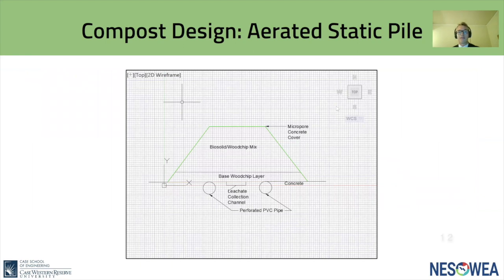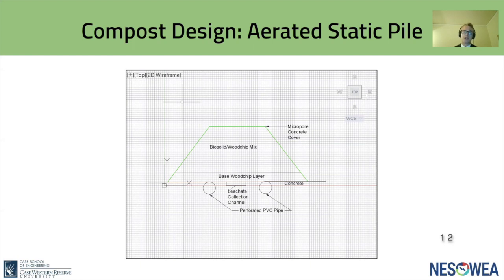We have chosen the aerated static pile composting method. This method involves the placement of a mixture of organic matter and bulking agent onto a system of perforated pipes which forcefully aerates the concoction. Aeration is key, as the process relies on micro-organisms breaking down the organic matter while consuming BOD. We also considered the windrow method, which similarly requires compost placed in long piles — known as windrows — but where aeration occurs through mechanical turning rather than forcefully through pipes. Aerated static pile was preferred due to reduced operation requirements and superior temperature controls, especially in Ohio, which experiences all four seasons.